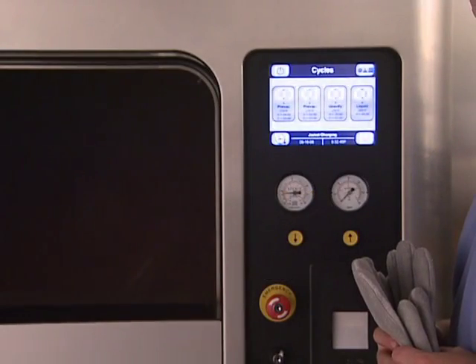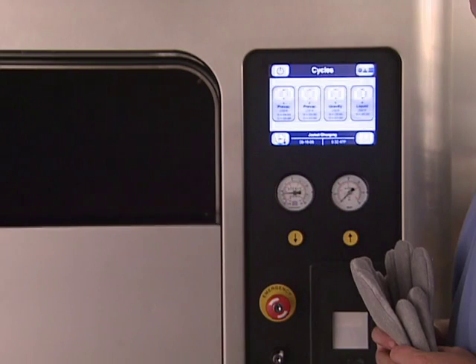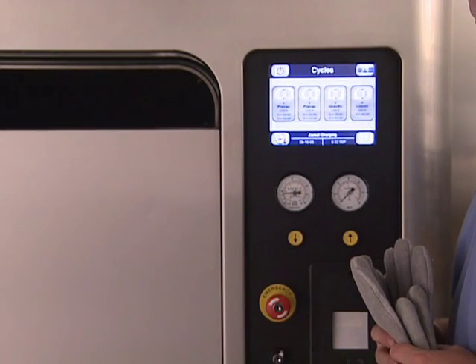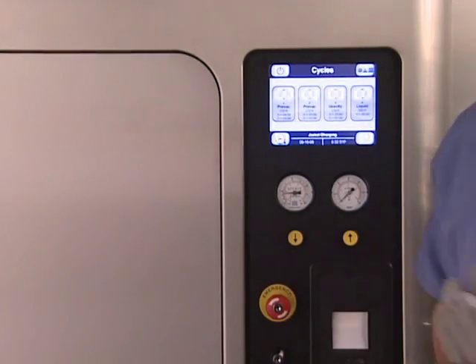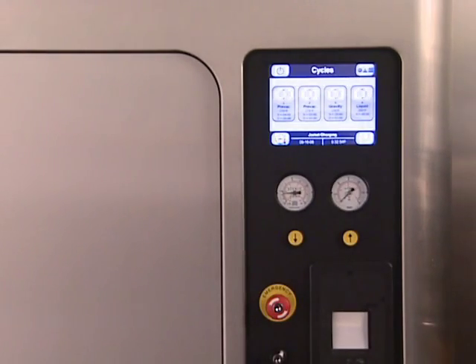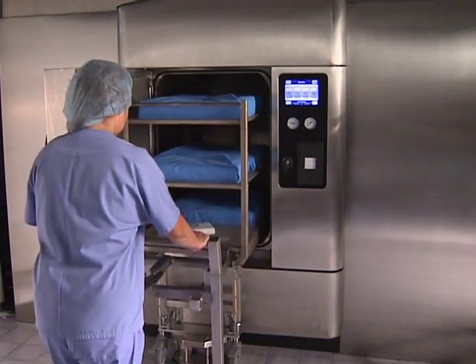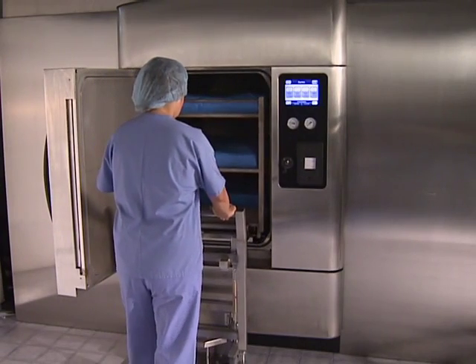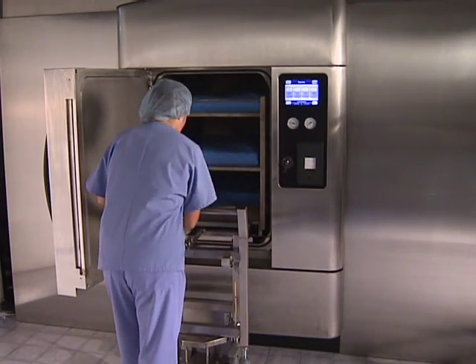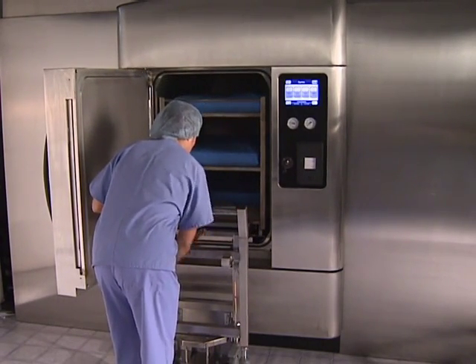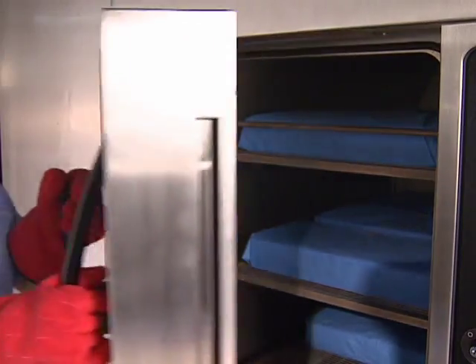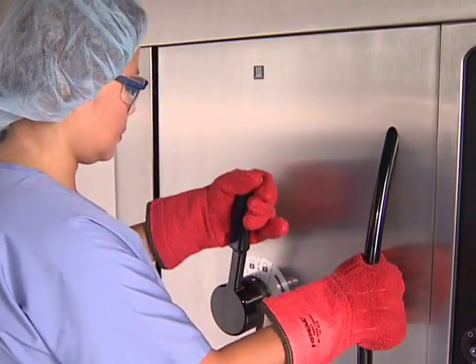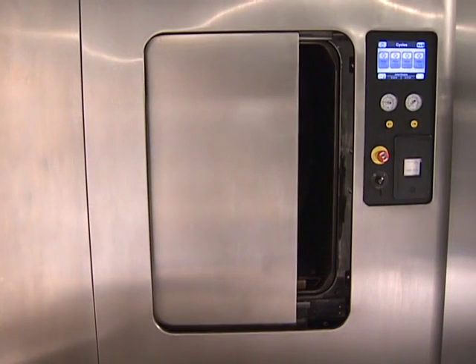Whether the door is manual or automated, be sure to keep the chamber door closed when the sterilizer is not in use. This conserves utilities and helps to optimize sterilizer operation. Each Evolution model has its own maximum quantity of wrapped instrument trays that it can process at one time. The 26-inch by 37.5-inch models feature an elliptical chamber and a manual hinged or automated horizontal door.